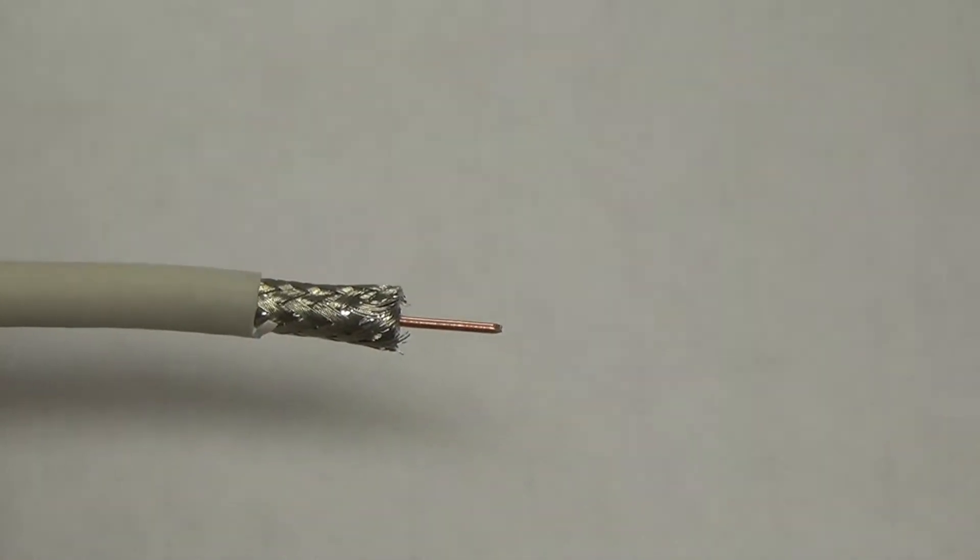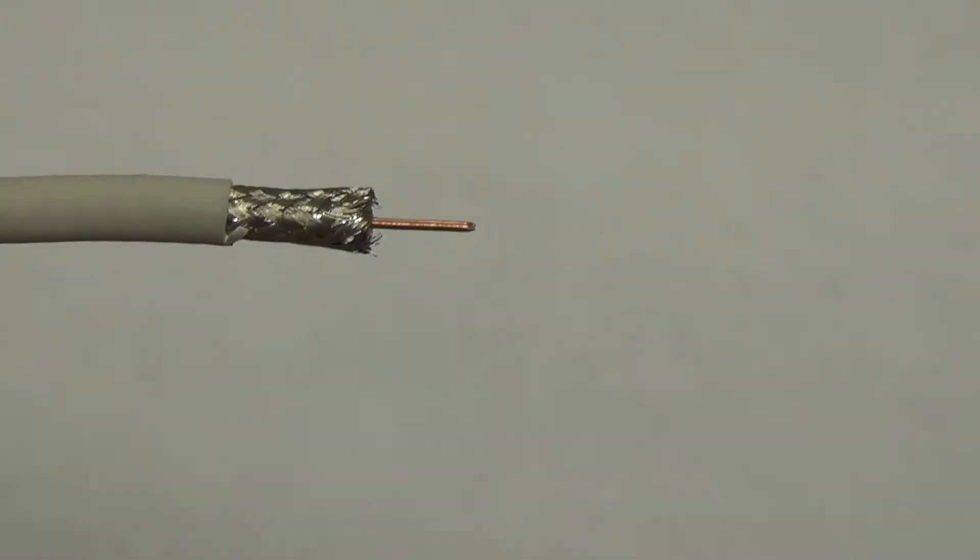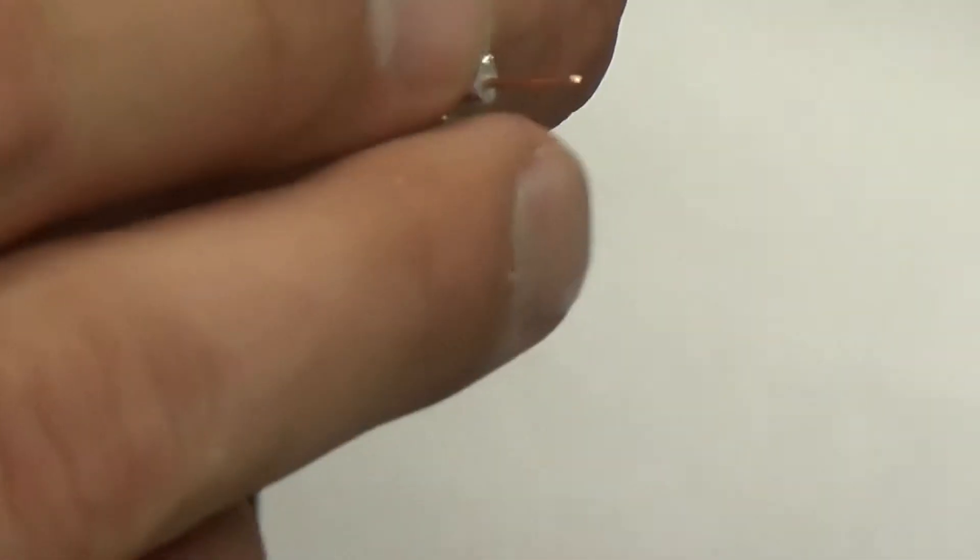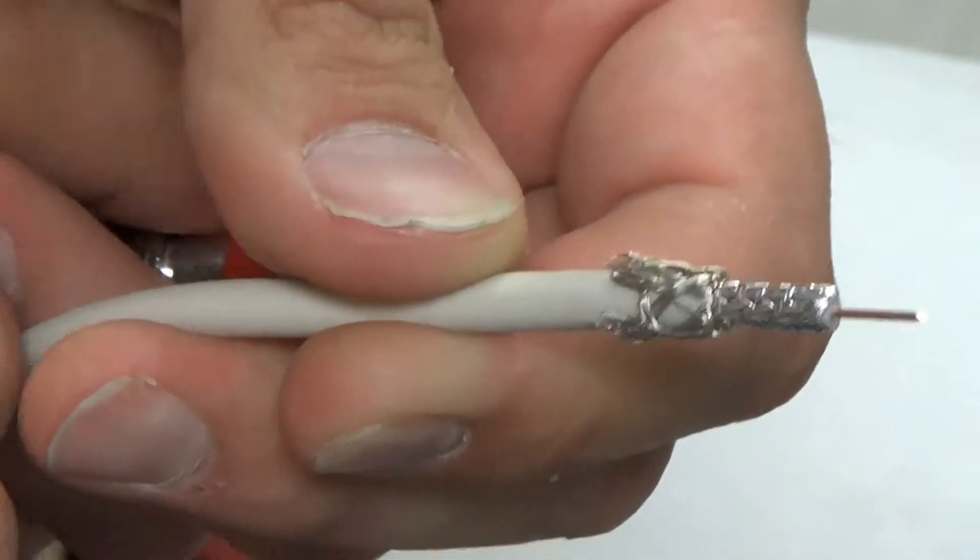Let's grab that ruler right there. So three-eighths of an inch is what we're looking at, and then we fold our foil back, our braid back. That's once again, that's a typical practice of making a connector - always fold back your braid on almost every single connector you ever make. Now there's different times on certain connectors you'd fold back, but on this one, it's this time.